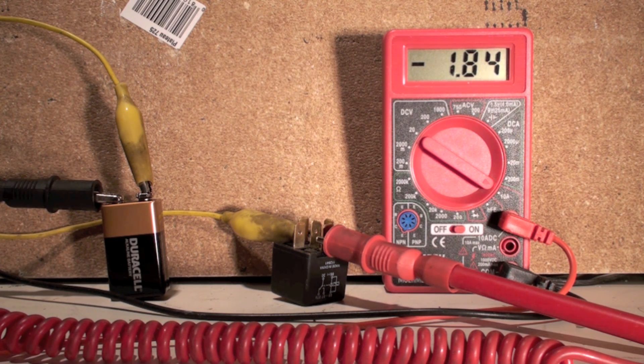It's a little convoluted, and in some cases it's the only way to do it if you're reading DC. There are meters that will read DC without putting them in line, and we'll talk about them later. But for the most part we're using AC and we can use clamp meters for this rather than putting it in line like that.